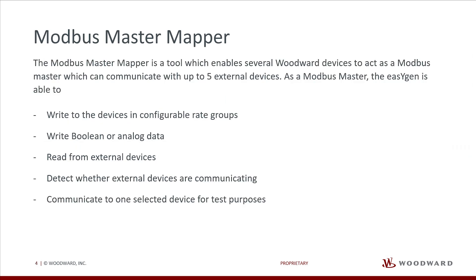The Modbus Master Mapper is a tool which enables several Woodward devices to act as a Modbus Master, which can communicate with up to five external devices. As a Modbus Master, the EasyGen is able to write to devices in configurable rate groups, write boolean or analog data, read from external devices, detect whether external devices are communicating, and communicate to one selected device for test purposes.